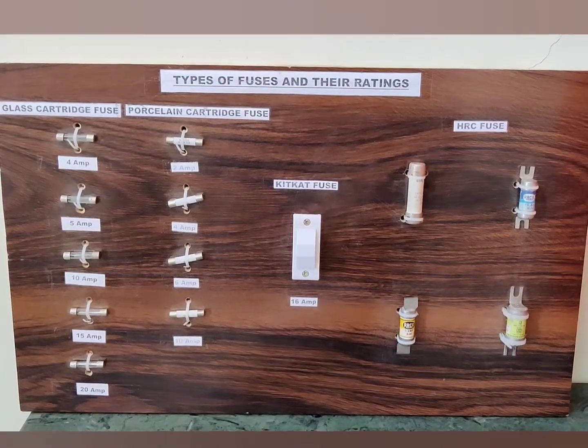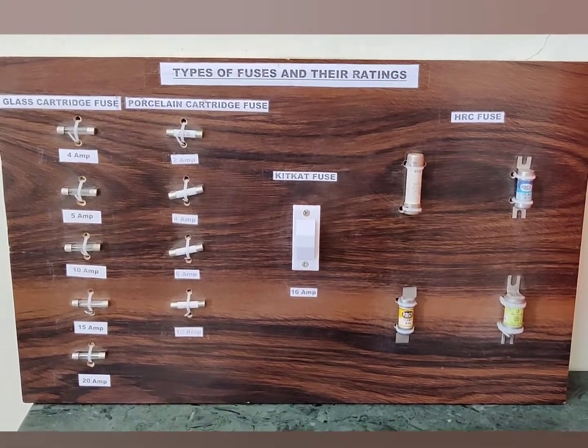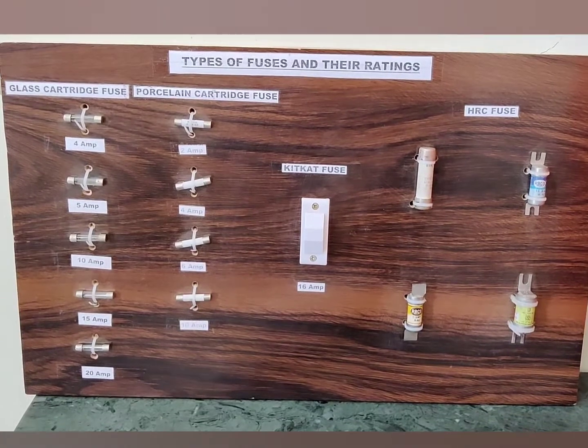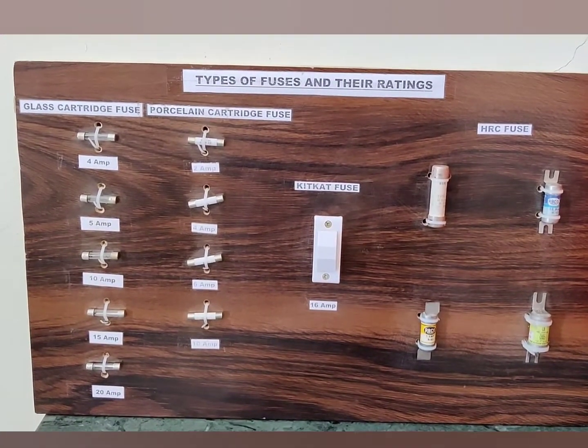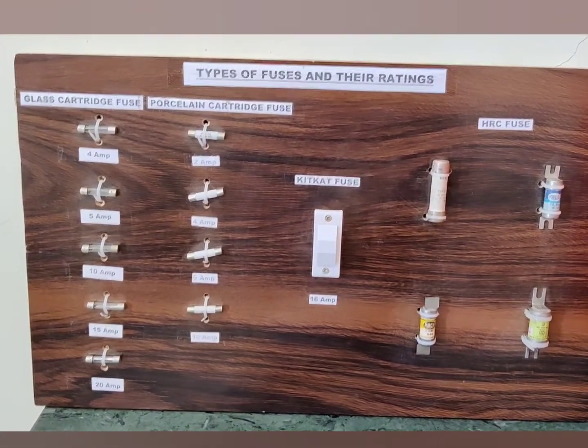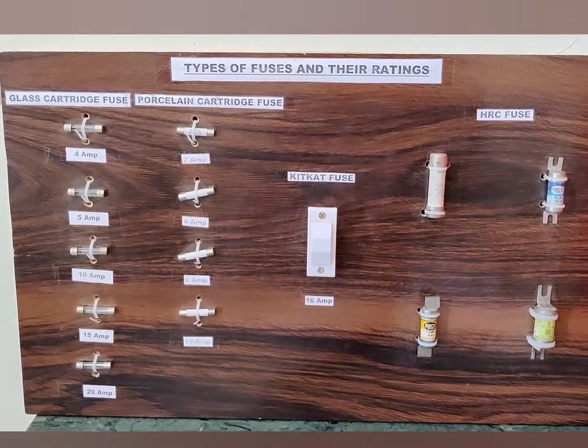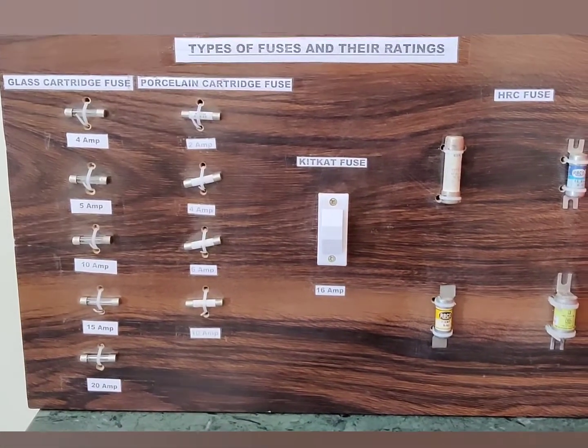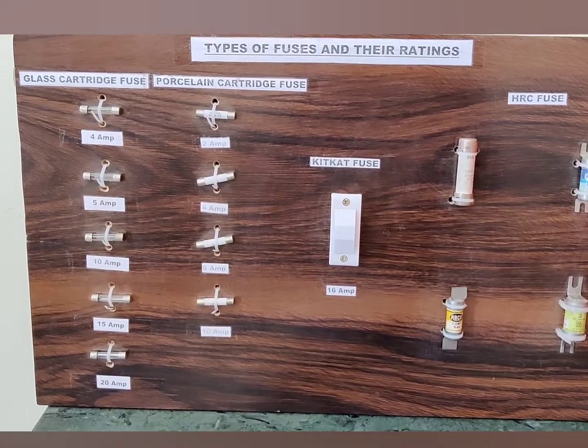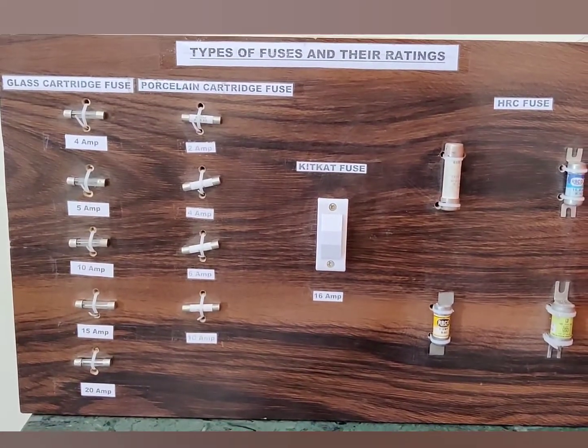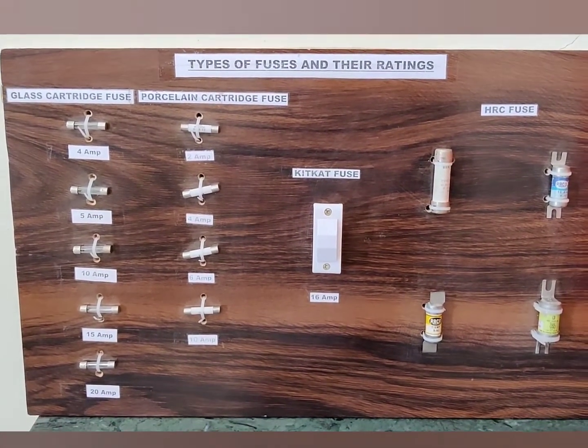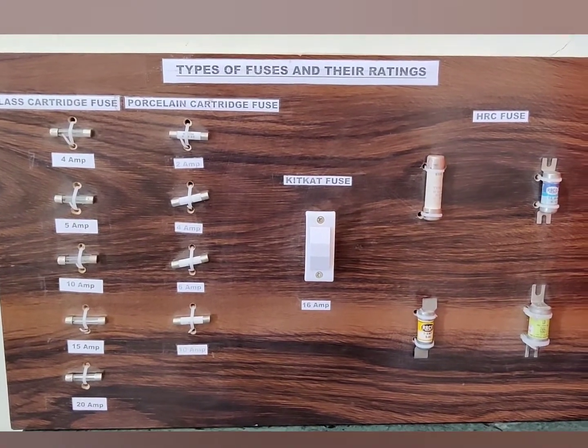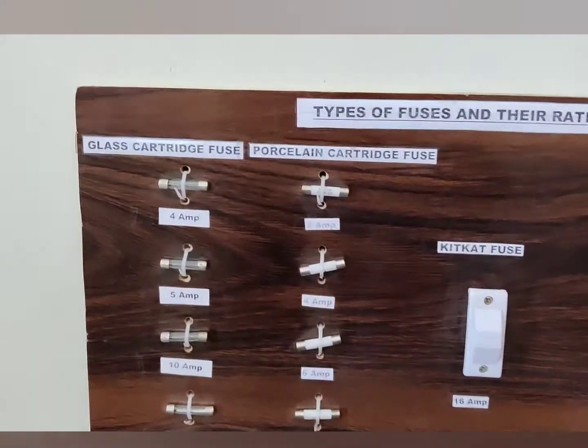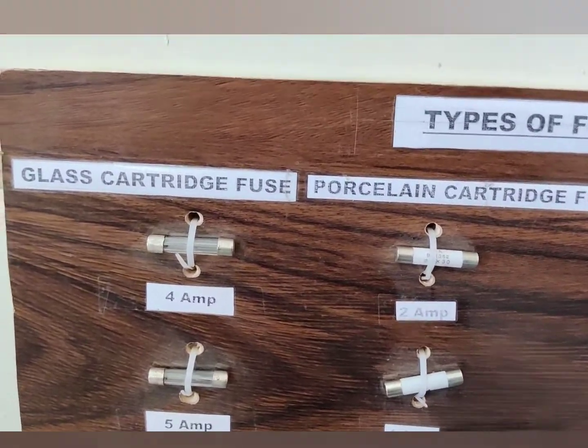Fuse is one of the most basic types of protective device which is used in the laboratories as well as at our homes. Fuses are of different types and they have different ratings depending upon their types. Basically, a fuse is a device which is used for overcurrent and short circuit protection in case of a fault. So here you can see that there are different types of fuses. First you can see that there are glass cartridge fuses.